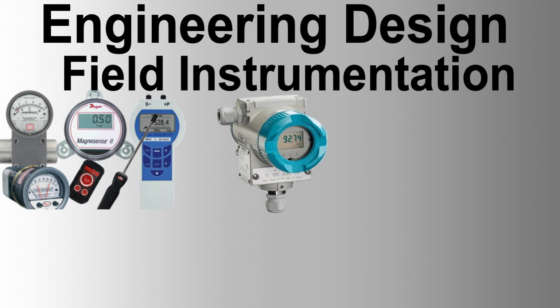Stainless steel tubing must be clearly marked at intervals along its length bearing e.g. ASTM A269 grade, size and molybdenum content. The tube must be externally protected with PVC sheath. Tubing for use on sour services must conform to NACE MR0175, latest. Standard stainless steel 316L tubing sizes must be as follows. However, larger wall thicknesses must be used where necessary to achieve the required pressure rating for the specific application.